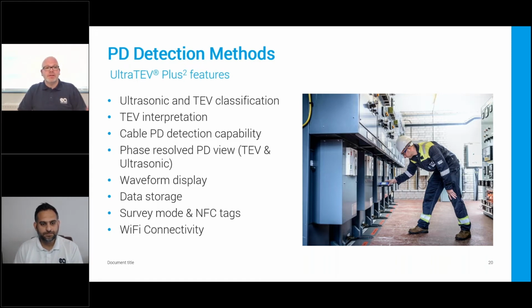It also has the capability to store data, to compare readings over time, essentially. So it uses NFC tags, or near field communication tags. They're literally just stuck onto the switchgear where the reading was taken, and then in whatever three to six months' time, whenever the next reading is done, a direct comparison can be made, which is obviously ideal for monitoring developing and growing levels of PD activity.